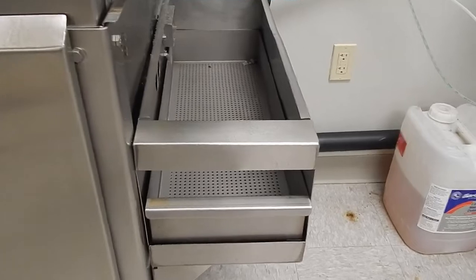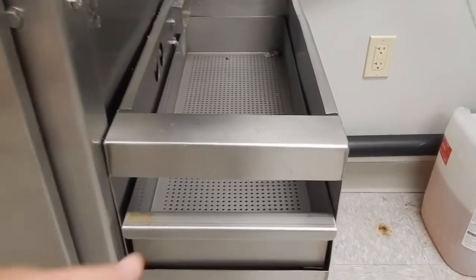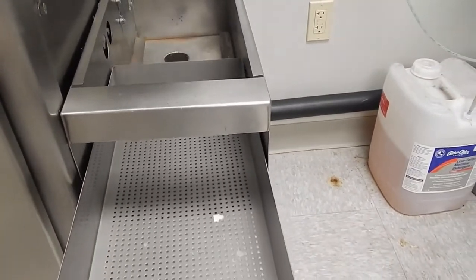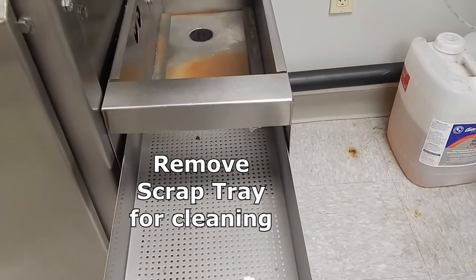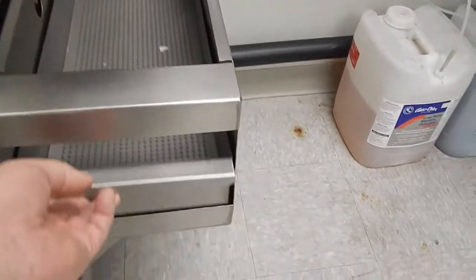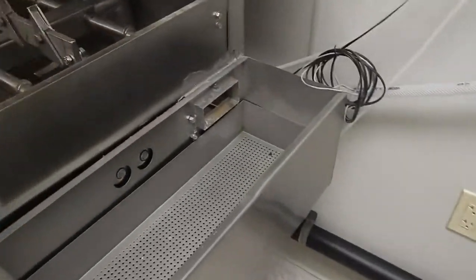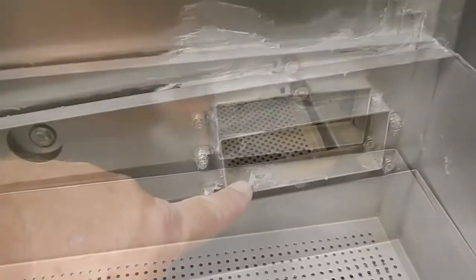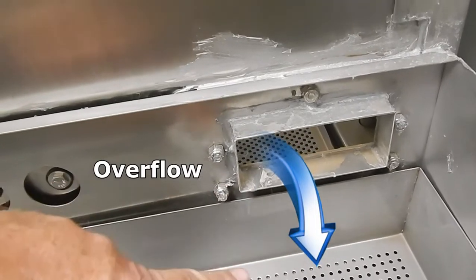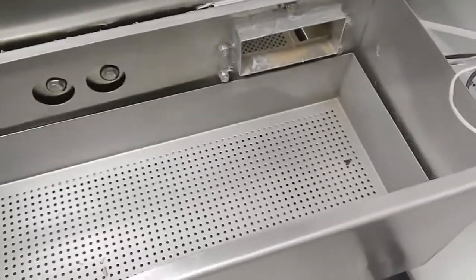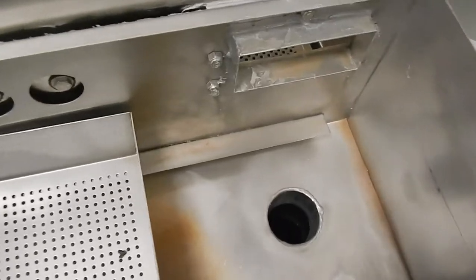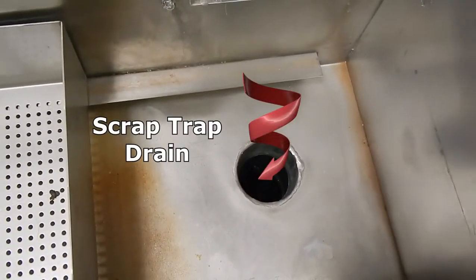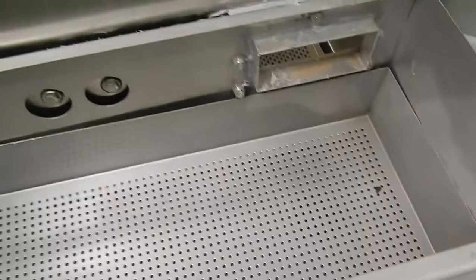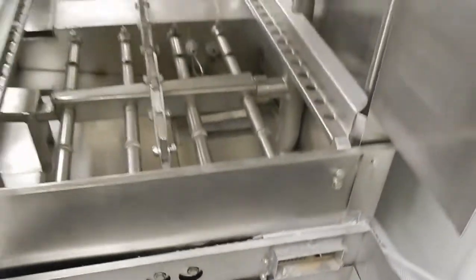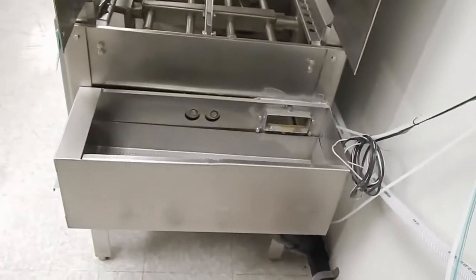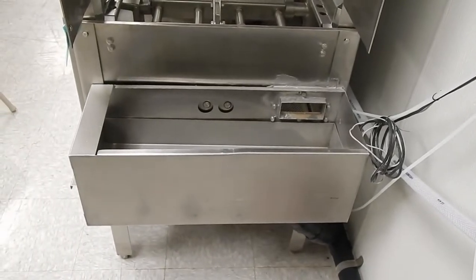The last component we look at is the scrap trap. The scrap trap has a removable tray that should be removed and cleaned. This is where the overflow from the wash tank flows into the scrap trap. Once it overflows, it actually flows straight to sewer or to drain through the scrap trap drain. This completes the inside service inspection of the AC44 conveyor.